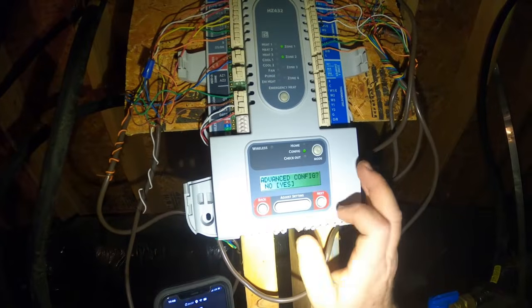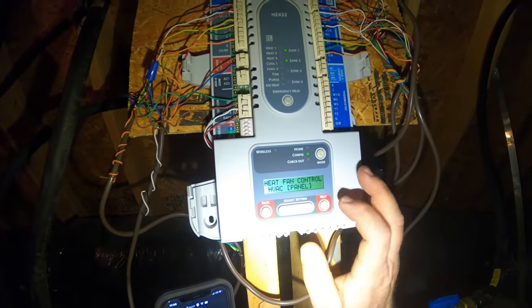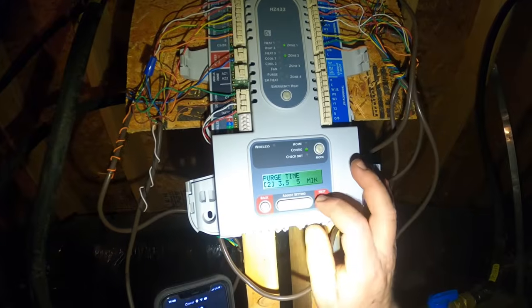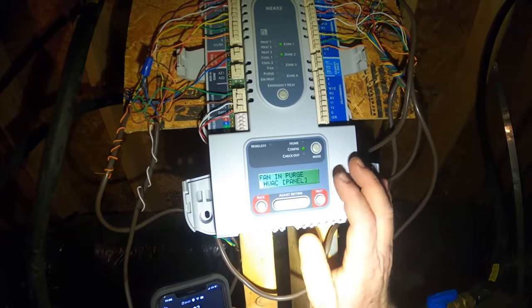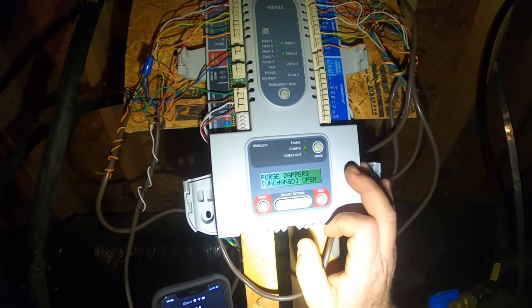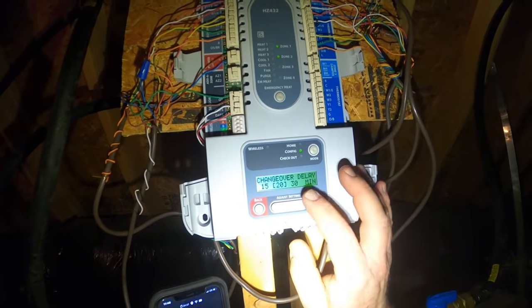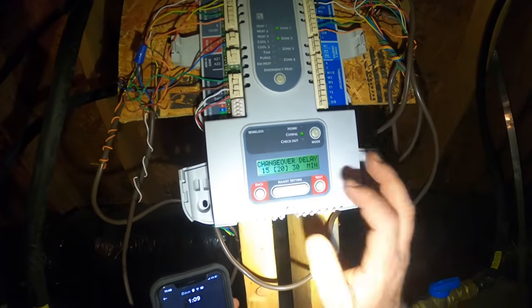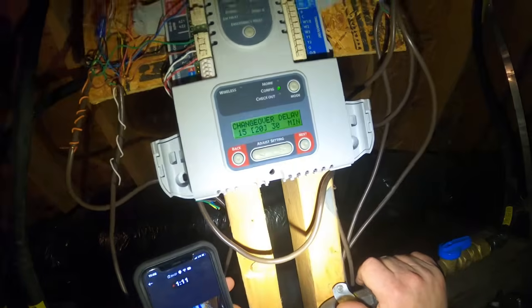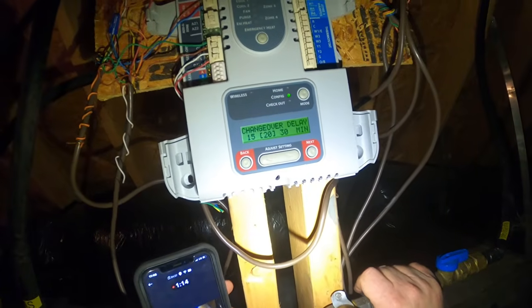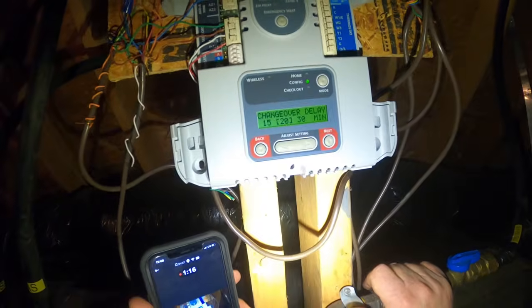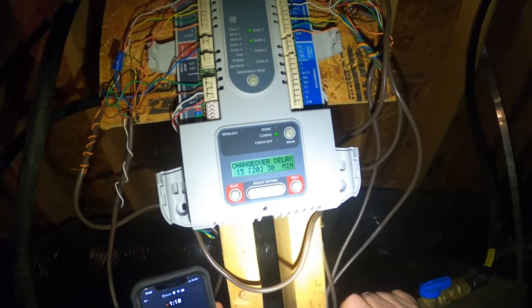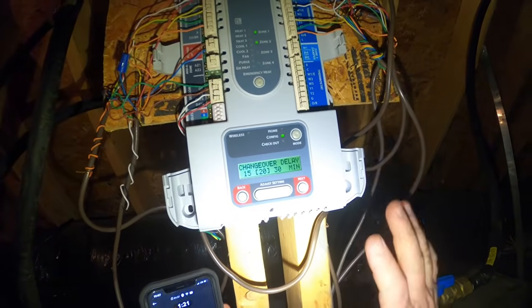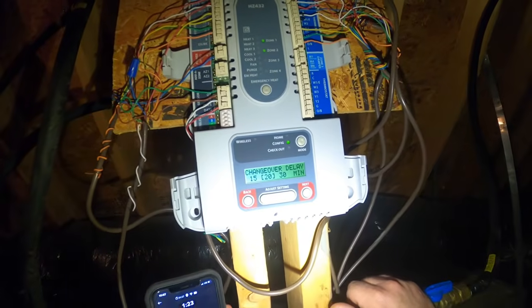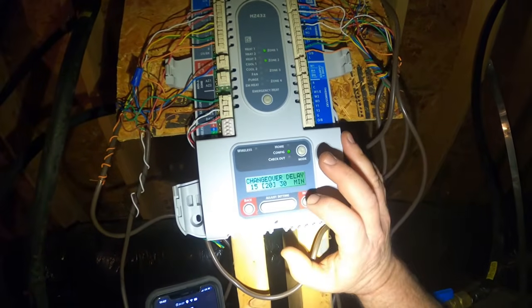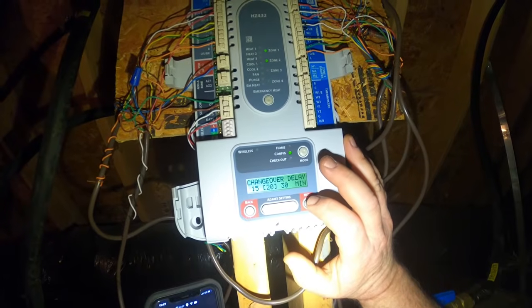Go into the advanced configurations, heat fan control, panel, purge time 2 minutes, fan and purge, let the panel control that. Purge dampers unchanged, we're going to leave that as it is. Changeover delay 20 minutes. That's if somebody's got one thermostat on cooling and one's on heating, it'll do a 20-minute delay. The last function, if one thermostat ran to heat and it satisfied, the other one calls for cooling, it's going to put a 20-minute delay on that. I don't recommend running thermostats in opposite modes with zoning, but it's possible.